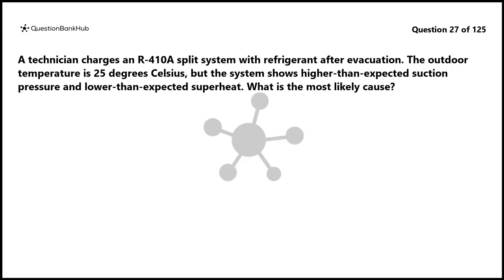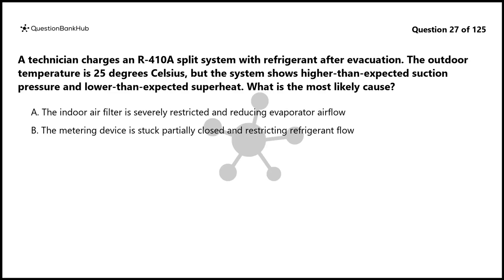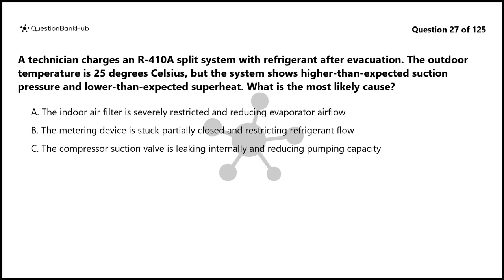Question 27. A technician charges an R410A split system with refrigerant after evacuation. The outdoor temperature is 25 degrees Celsius, but the system shows higher than expected suction pressure and lower than expected superheat. What is the most likely cause? A. The indoor air filter is severely restricted and reducing evaporator airflow. B. The metering device is stuck partially closed and restricting refrigerant flow. C. The compressor suction valve is leaking internally and reducing pumping capacity. D. The system has been overcharged with refrigerant beyond the required amount.